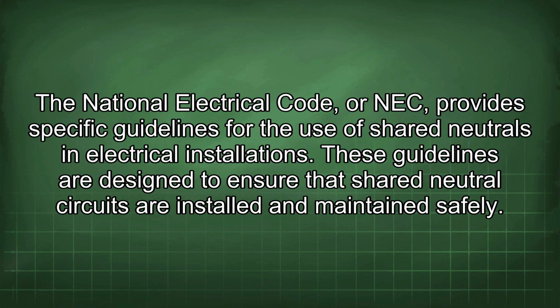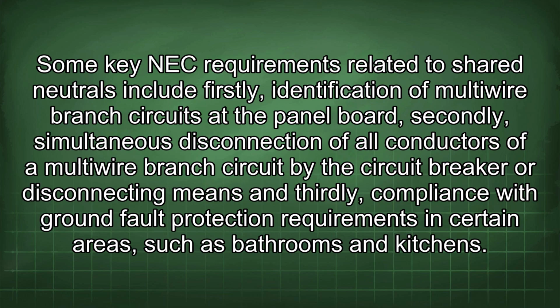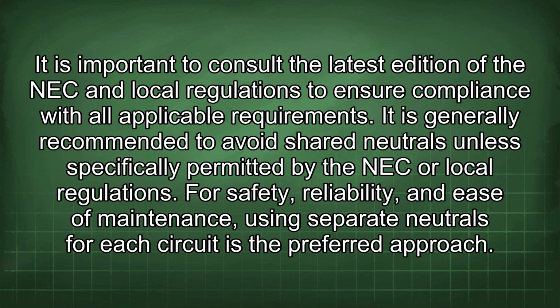The National Electrical Code, or NEC, provides specific guidelines for the use of shared neutrals in electrical installations. These guidelines are designed to ensure that shared neutral circuits are installed and maintained safely. Some key NEC requirements related to shared neutrals include: firstly, identification of multi-wire branch circuits at the panel board; secondly, simultaneous disconnection of all conductors of a multi-wire branch circuit by the circuit breaker or disconnecting means; and thirdly, compliance with ground fault protection requirements in certain areas, such as bathrooms and kitchens. It is important to consult the latest edition of the NEC and local regulations to ensure compliance with all applicable requirements.